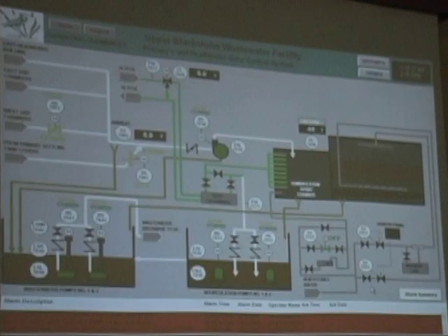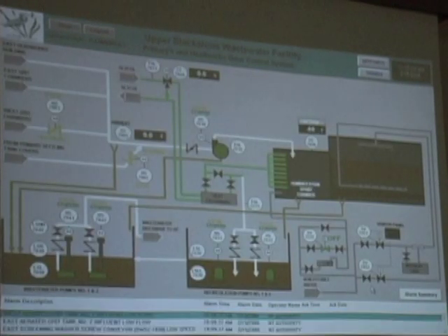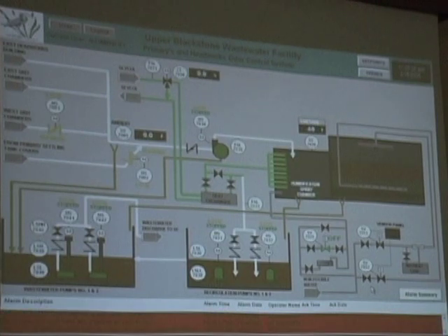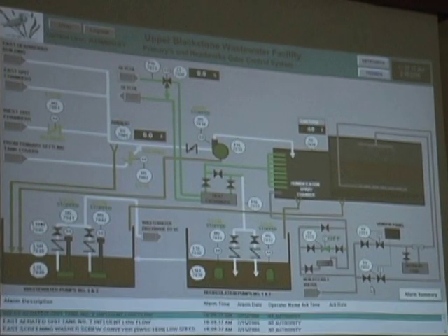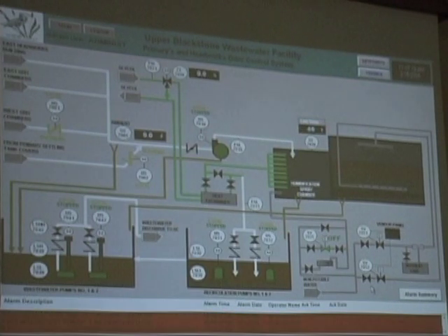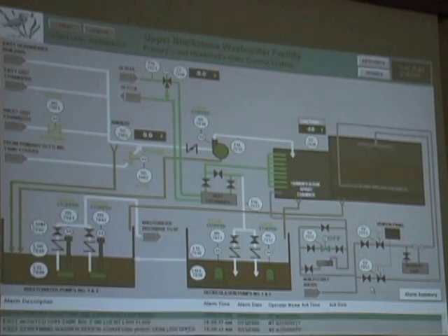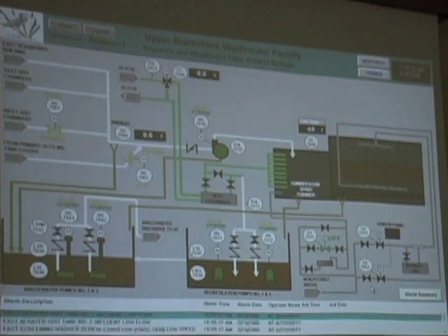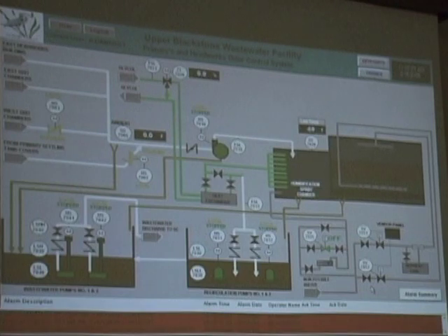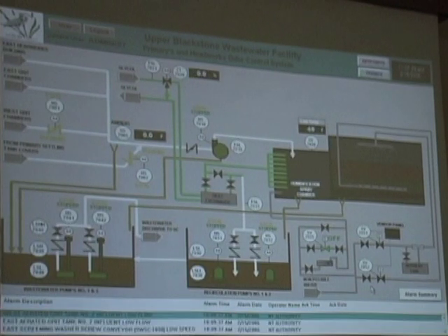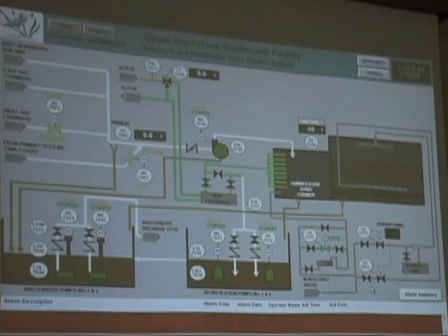Can we just back it up a little bit too? Sure. On this comm loss, if we get that alarm, how can we still keep that piece of equipment online? If you get that alarm, that means that it might be continuing to run, but you're no longer communicating to it. Okay. That was the whole reason that I was trying to explain that these are Ethernet drives, meaning that there's one cable from our processor to their processor, for lack of a better term.